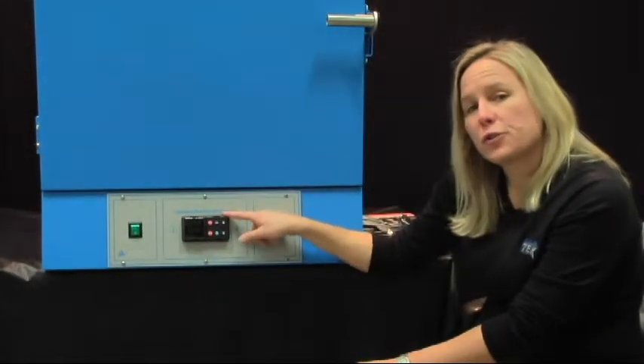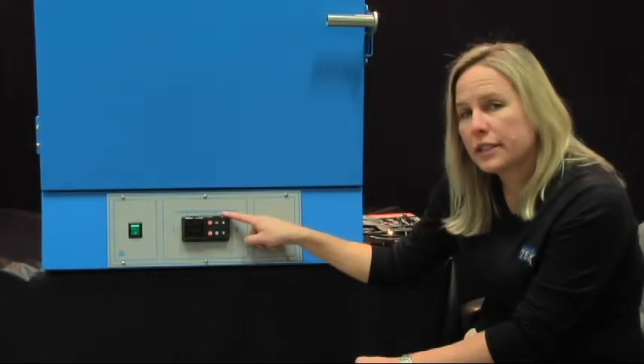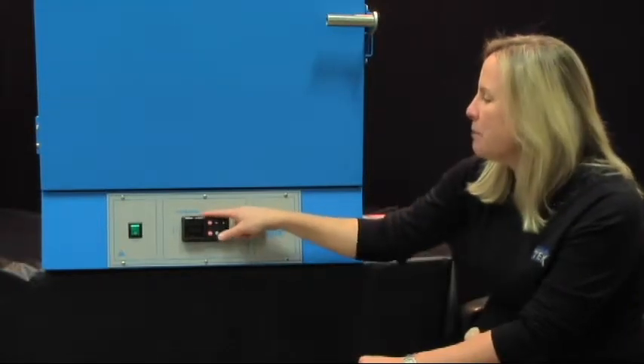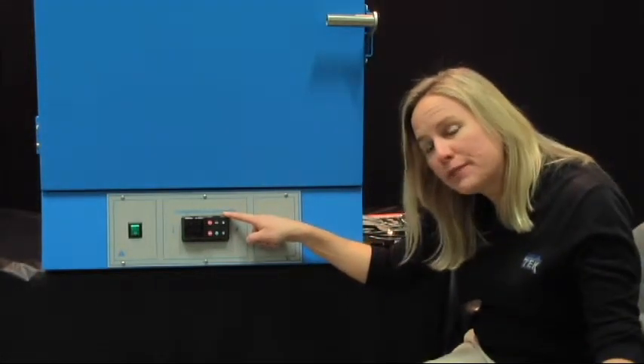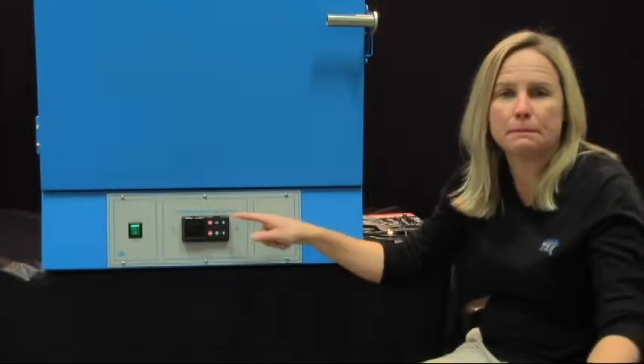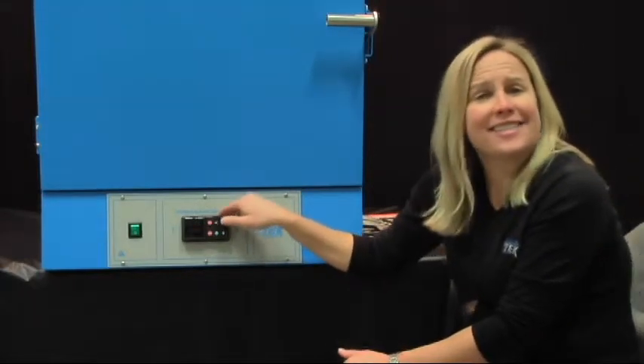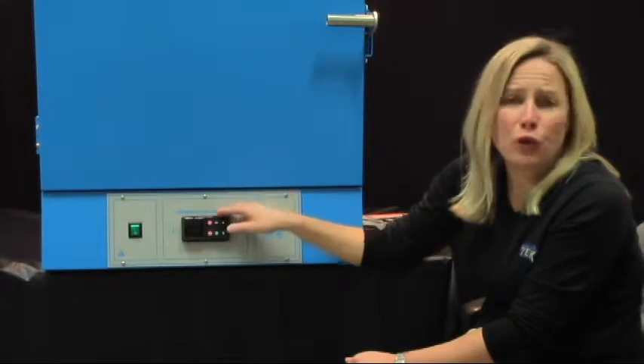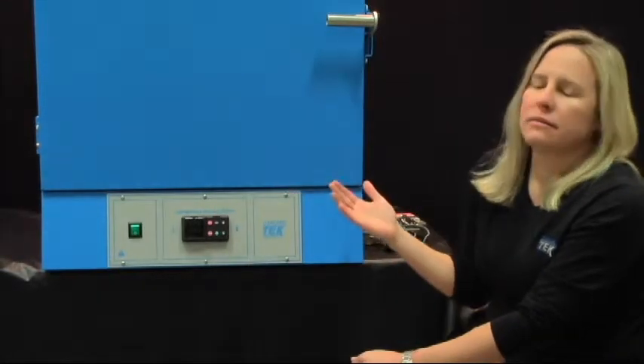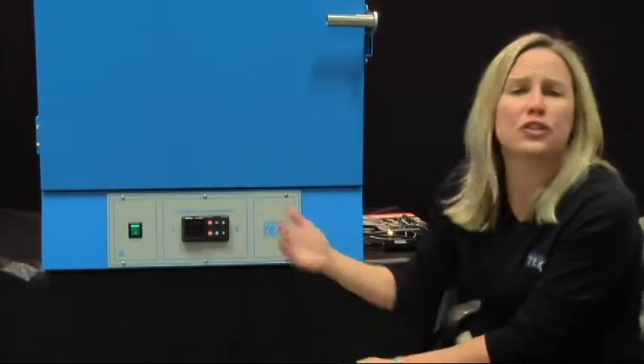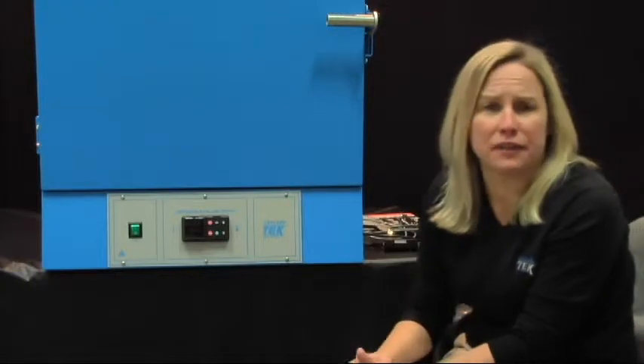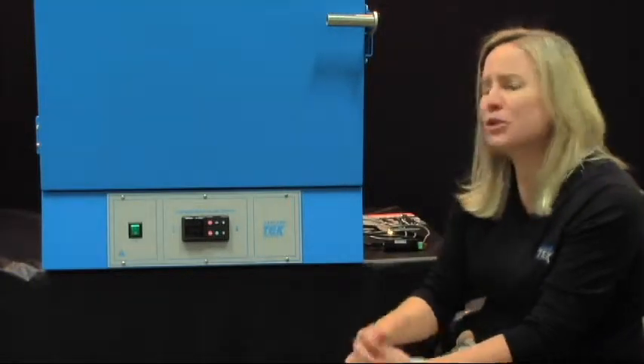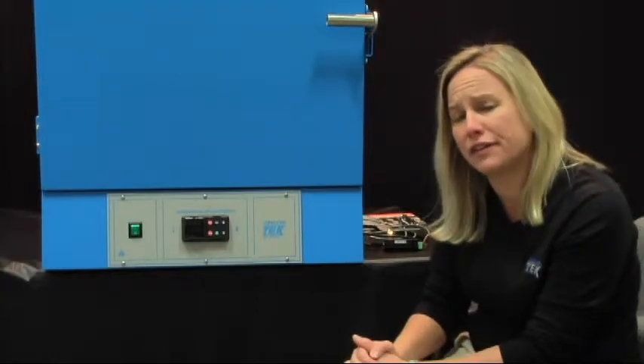Another feature that's really great about the Watlow controller on our TFO ovens is that it has a built-in high limit control, sometimes called an over-temp protection fail-safe device. This is something that you'll need to set before you use your oven. Let's say, for example, what you're putting in the oven will be destroyed at 200 degrees C, or it's very expensive and you would like to protect it, but you know you want to dry it at 150 degrees C.